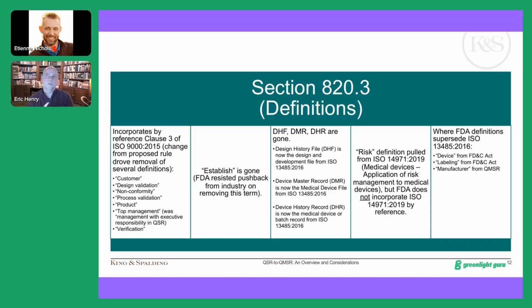Where this gets really interesting from a structural point of view in the quality system is that if you remember, the definition in 820.3 of the current QSR defines design outputs. And that definition says that a finished design output constitutes the packaging, labeling, the medical device itself, and the device master record. So the device master record is a finished design output. And because it's a design output, that makes it part of the design history file. So the DMR, in effect, is a subset of the design history file. Well, that sort of embedding of one file type into another is gone. The medical device file sits here, the design and development file sits here. There will be some overlap, surely, but that concept of one sitting within another is basically gone.